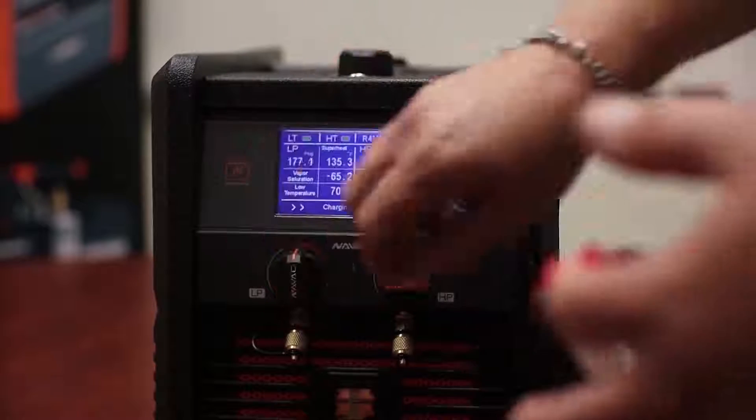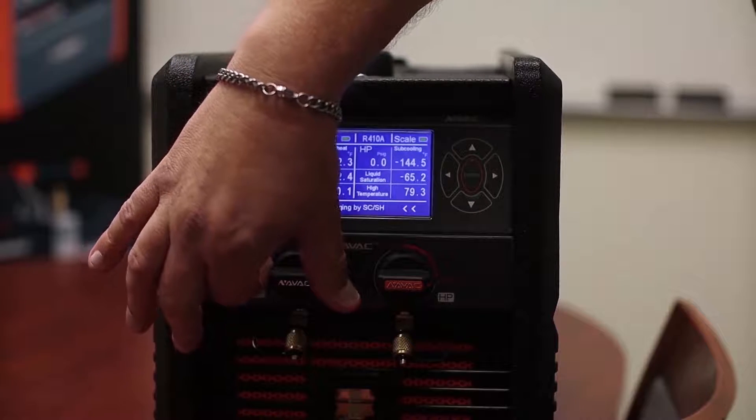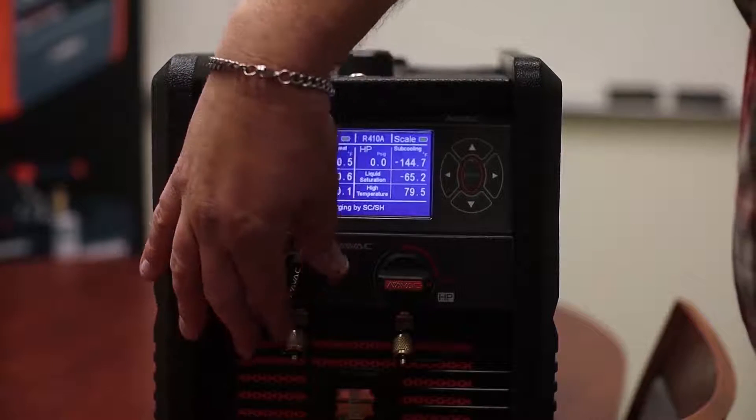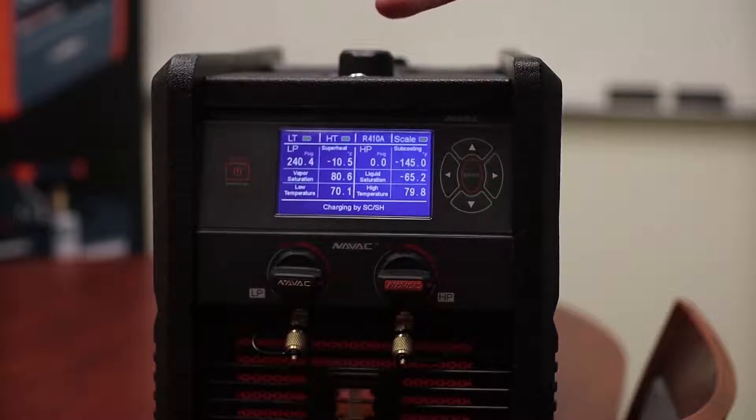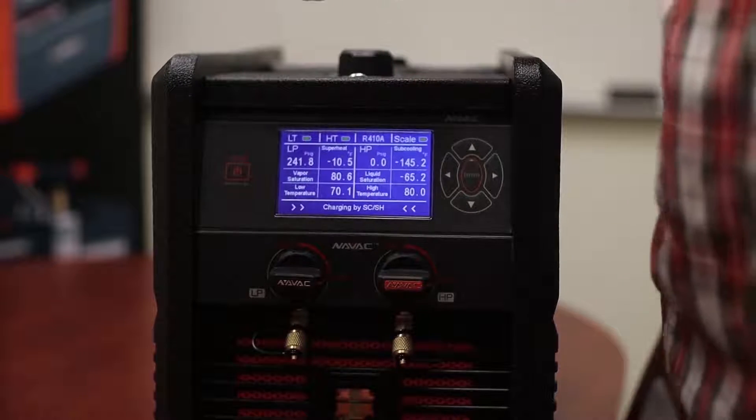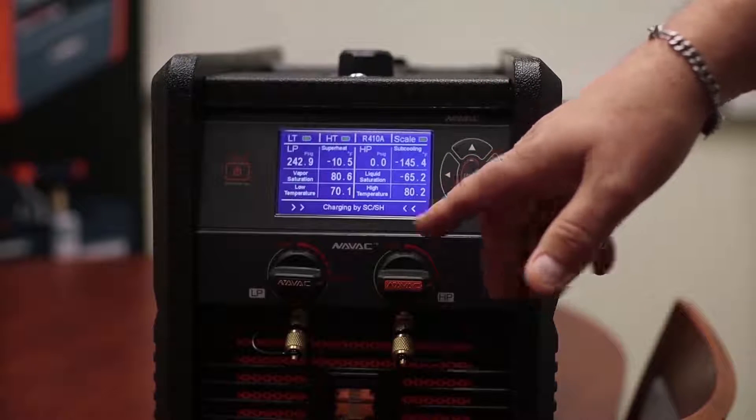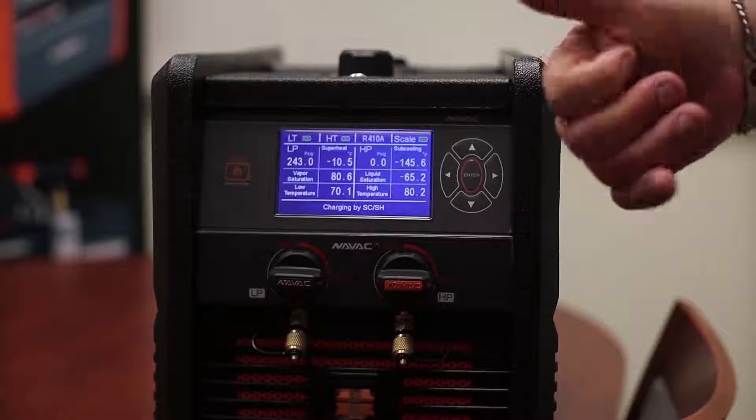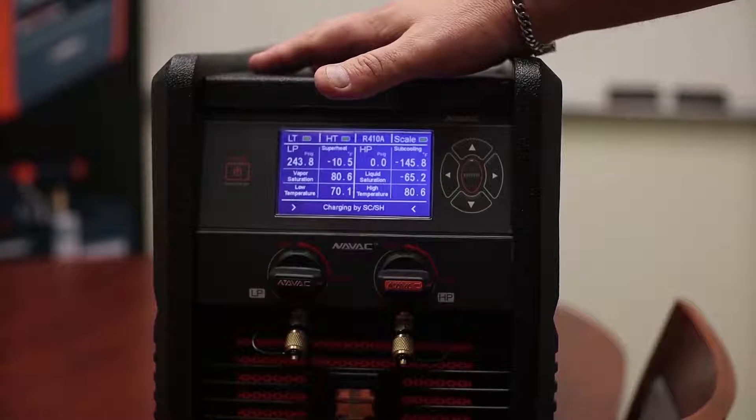The only valve open at this point in time or valves internally is the inlet and the outlet on the vapor side. So this is the low side of your manifold gauge. You're going to throttle in the refrigerant just like you would using a digital manifold gauge with temperature probes. So again, using subcooling, superheat, you're the technician. You need to understand how to do it. The machine doesn't do it for you.